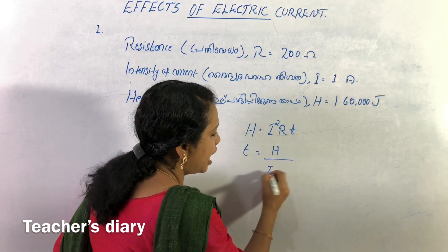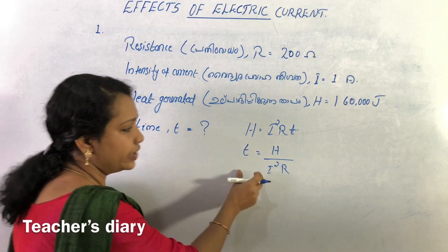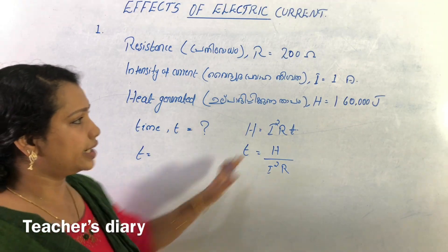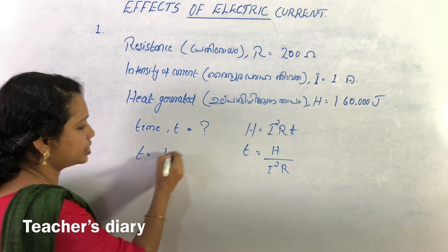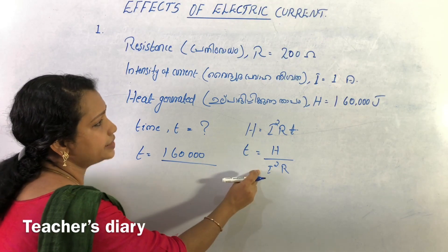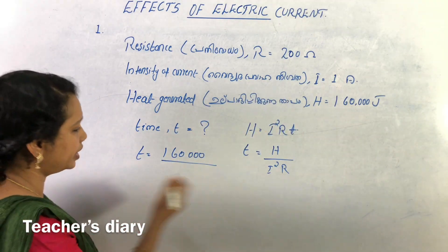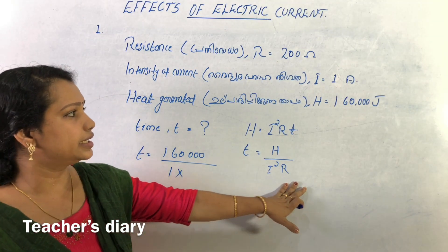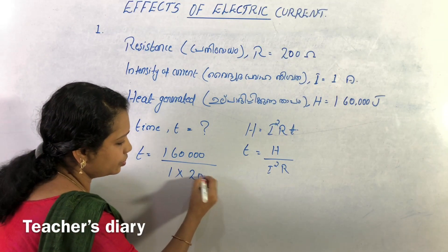T is equal to H divided by I squared into R. We substitute values: H is 1,60,000. I is 1 ampere, so I squared is 1. Resistance is 200 ohms.